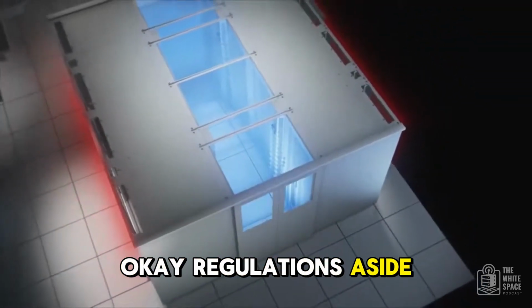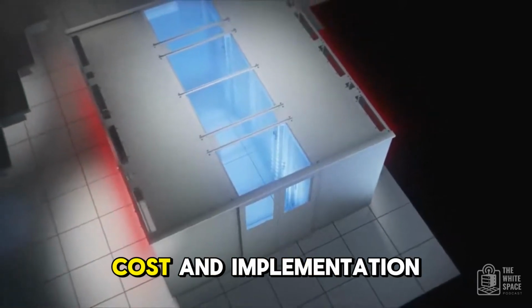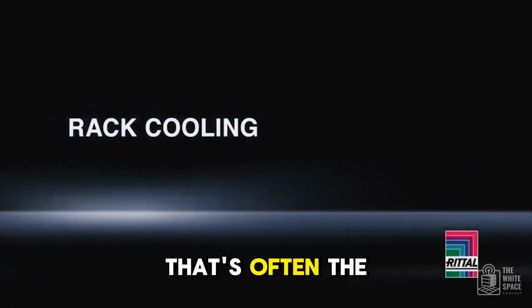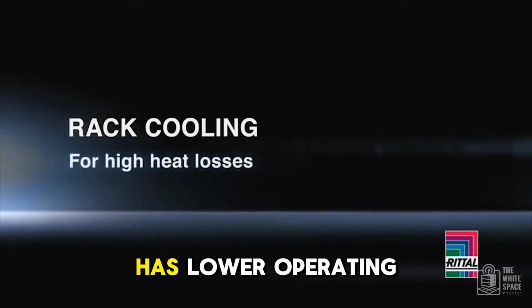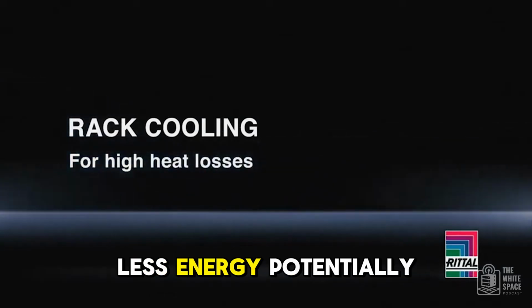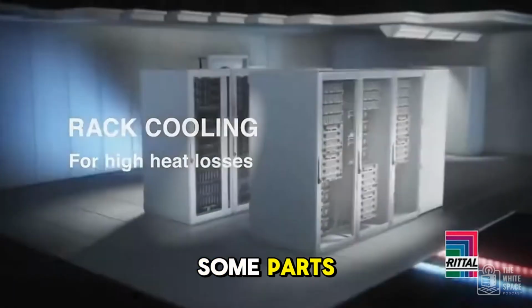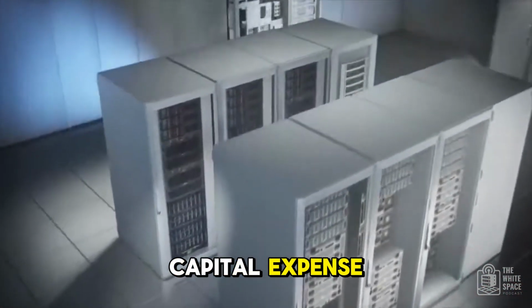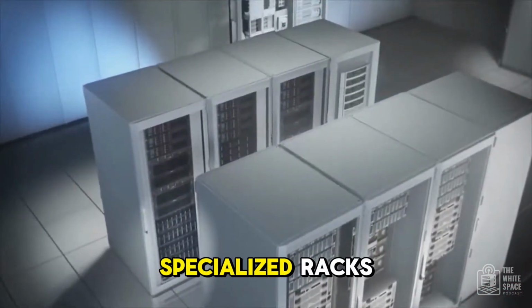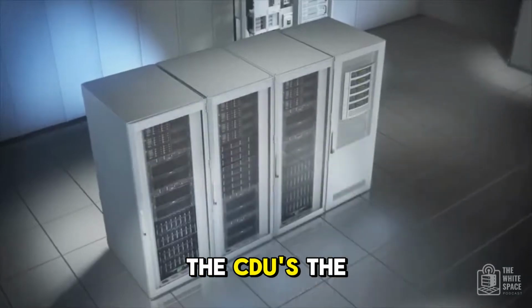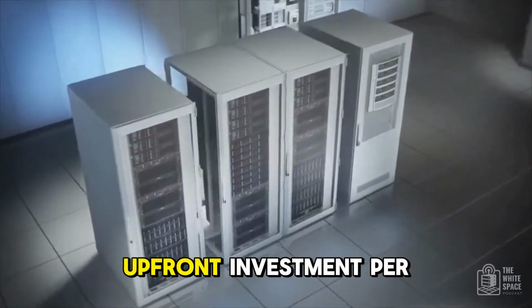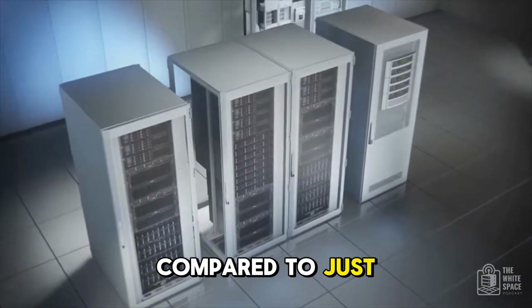Okay, regulations aside, there's always the bottom line: cost and implementation. Liquid cooling sounds great for operating costs, but getting started seems expensive. That's often the trade-off. Liquid cooling usually has lower operating expenses, less energy, potentially less maintenance on some parts. But the initial capital expense, the CapEx, can be higher. You might need specialized racks, the CDUs, the piping. It's a bigger upfront investment per rack compared to just adding another air handler.